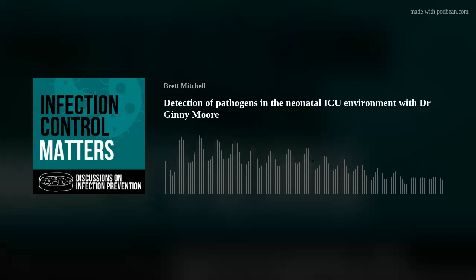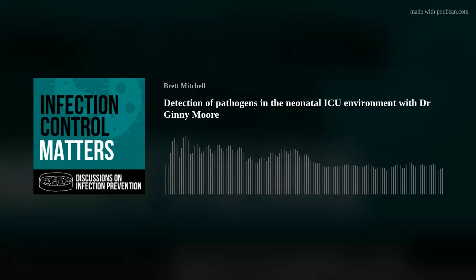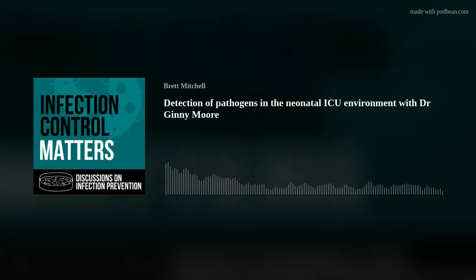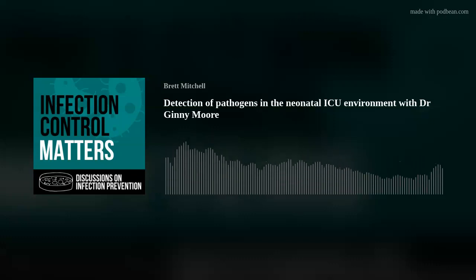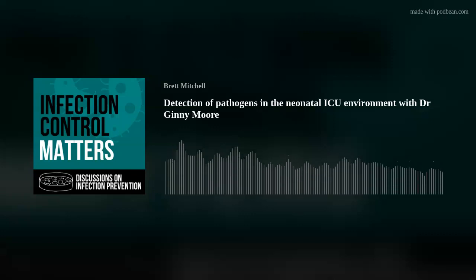I think one of the areas we want to look at in a bit more detail, in all likelihood to rule it out as any kind of risk, is the fan within the base of the unit. If you look at desktop fans around the place, they're normally covered in what we call gunk. Were the fans visibly clean? Because that certainly would disseminate again, wouldn't it? Yeah, so again, it differed between units. That could be because of the age of the incubator, or differences in cleaning protocol. But certainly that's one area that would be quite interesting to investigate a bit further, just to rule out anything more than anything else.